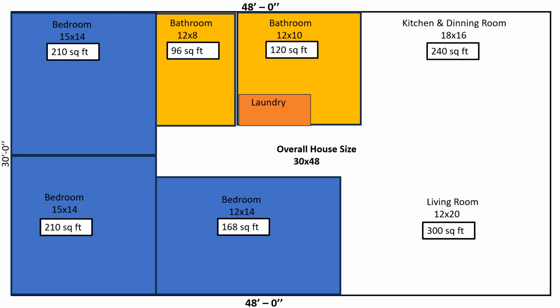So the next thing we're going to do is take our 2.8, look at that, and go on up. Since we have a higher ceiling here, we're going to go to a 3-ton. So a 3-ton is 1200 CFM. So it's 400 CFM per ton. So 4 times 3, 1200 CFM. So we're going to take our 1200 CFM and divide it by the 1440 that is our square feet, and you get a 0.83. Now, we're going to share something with you on this number.